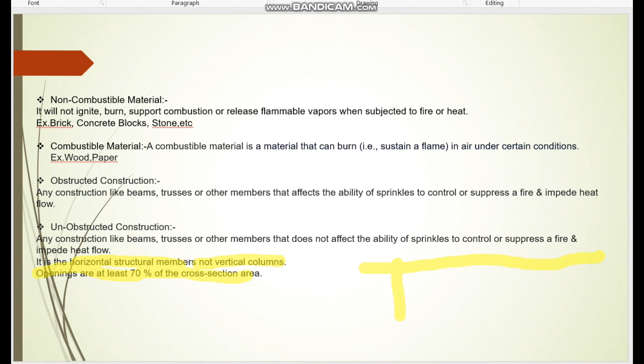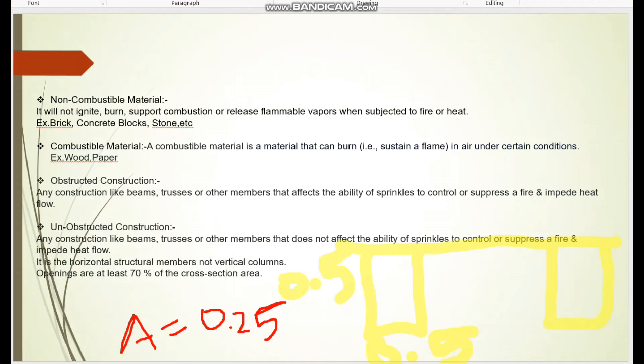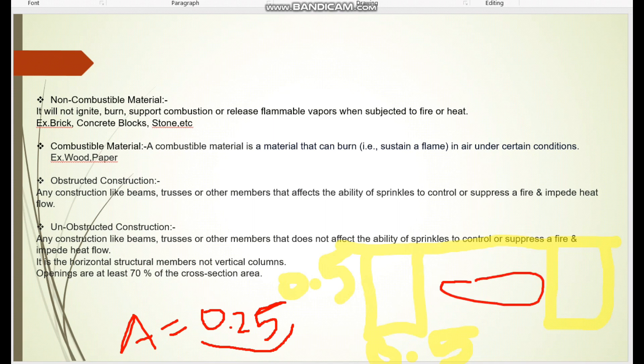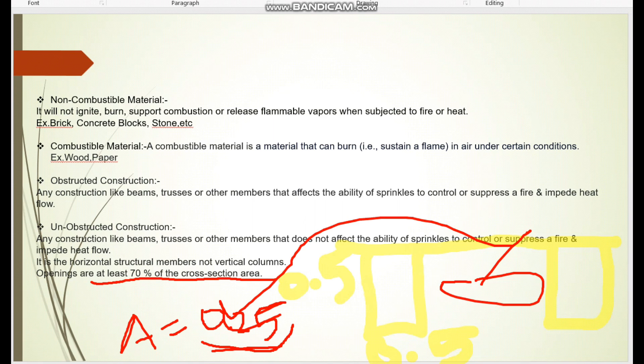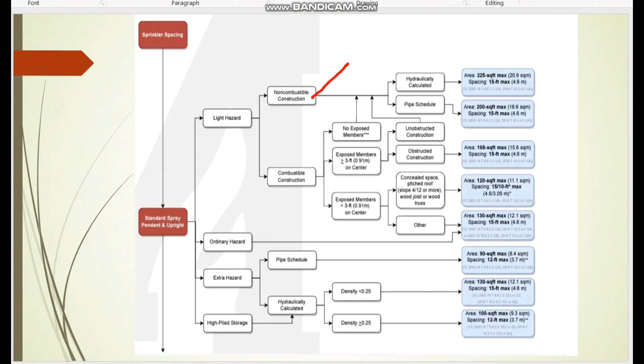Consider an arrangement with one structural member on each side — if this height is 0.5 m and this height is also 0.5 m, the total cross-sectional area is 0.5 × 0.5 = 0.25 m². The openings, meaning the open area, must be at least 70% of this cross-sectional area of 0.25 m². If all these conditions are combined and met, the construction qualifies as unobstructed.